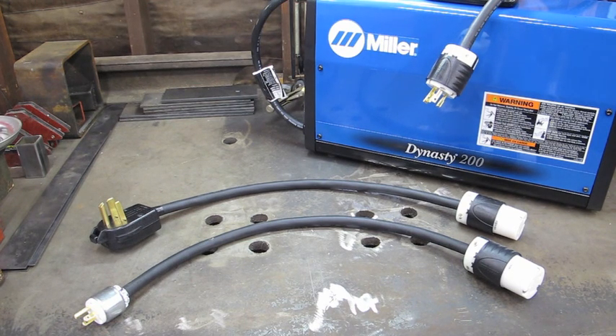Here in my shop I have a 50 amp 240 volt outlet — in fact I have a couple of them. But what if I take this to a buddy's house or to a job somewhere at a residence, somewhere that doesn't have a 240 to 250 volt receptacle readily available? And what if I don't have a generator, which I don't? Well, the obvious solution is to run it on household current, but if I wire this thing for 240, then I have to rewire it at another time for 120, and that's just not going to work. So the solution is these two adapters, which I created.